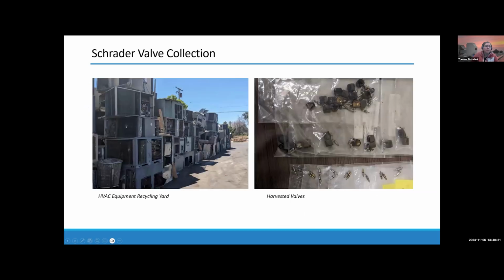Here's just a quick picture of our valve harvesting and the valves we picked up. Notice, obviously, this equipment is at end of life. We don't really know how old this equipment is or how old these valves are, but in my mind this is kind of a worst case scenario. The valves might leak more than you might find on the roof, because this is equipment that's essentially at the end of its life.